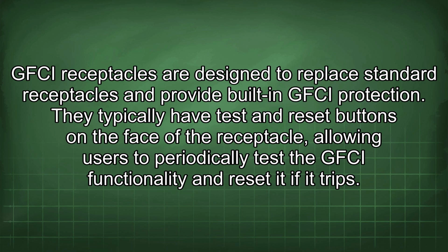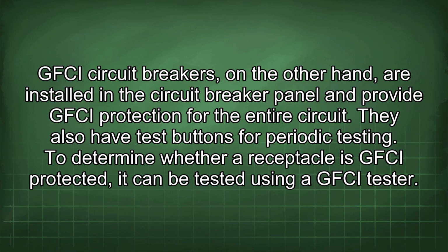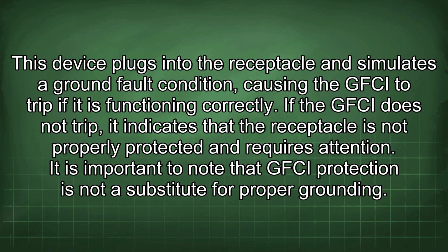GFCI receptacles are designed to replace standard receptacles and provide built-in GFCI protection. They typically have test and reset buttons on the face of the receptacle, allowing users to periodically test the GFCI functionality and reset it if it trips. GFCI circuit breakers, on the other hand, are installed in the circuit breaker panel and provide GFCI protection for the entire circuit. They also have test buttons for periodic testing. To determine whether a receptacle is GFCI protected, it can be tested using a GFCI tester. This device plugs into the receptacle and simulates a ground fault condition, causing the GFCI to trip if it is functioning correctly. If the GFCI does not trip, it indicates that the receptacle is not properly protected and requires attention.